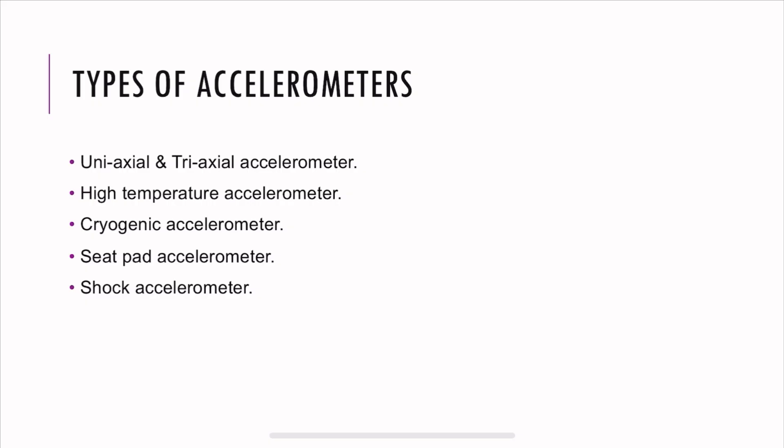You cannot use a regular accelerometer because it might damage. So you need a special high temperature accelerometer. It has some water cooling with some connections. You also have cryogenic accelerometers. So it's the opposite of high temperature, like extreme low temperatures, and you still want the accelerometer to be working. You have seat pad accelerometer, shock accelerometer, and many more.